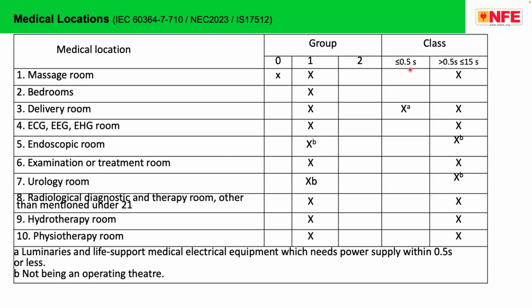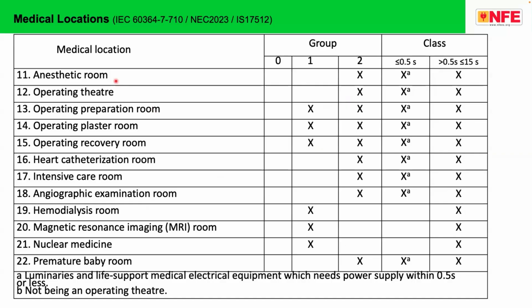On the right side, you can also see the class. This is the class of power supply, the maximum allowed time for the changeover in case of power failures, changeover from one source to the other source. Similarly, anesthetic room is classified as a Group 2 location, operation theater as a Group 2 location, and operation preparation room can be Group 1 or Group 2. It depends on the activity which is going on.